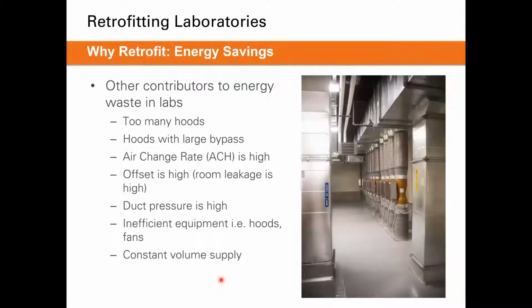Some other contributors to energy waste in labs could be too many hoods. So if your lab is unnecessarily fume hood dense, and maybe people aren't using the hoods as actual test spaces, maybe they're just using them for storage, that's an opportunity to swap that out for more efficient equipment, a cabinet for example. If the hoods have too large of a bypass, requiring more air than really necessary to flow through, that would also lead to excess ventilation. And all of these are related to ventilation. So that's where we're going to focus.